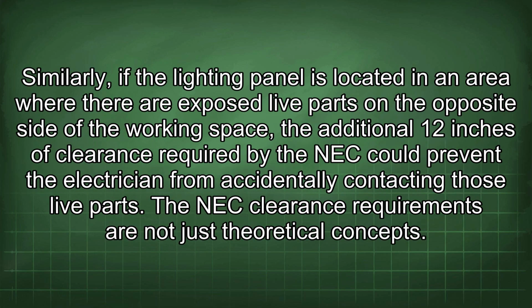Similarly, if the lighting panel is located in an area where there are exposed live parts on the opposite side of the working space, the additional 12 inches of clearance required by the NEC could prevent the electrician from accidentally contacting those live parts. The NEC clearance requirements are not just theoretical concepts.